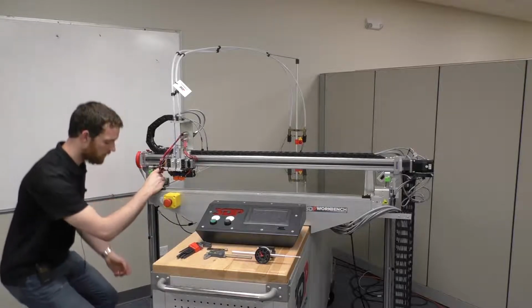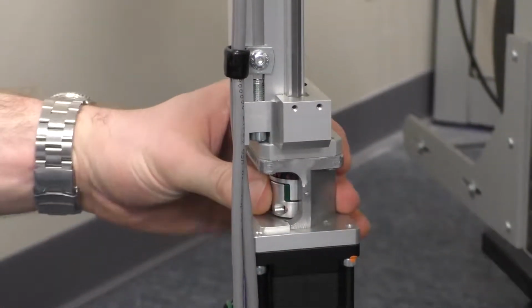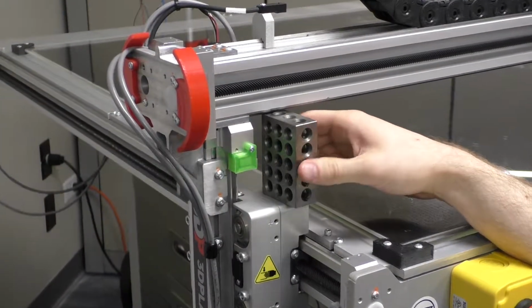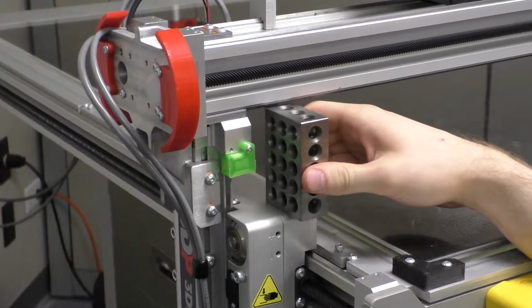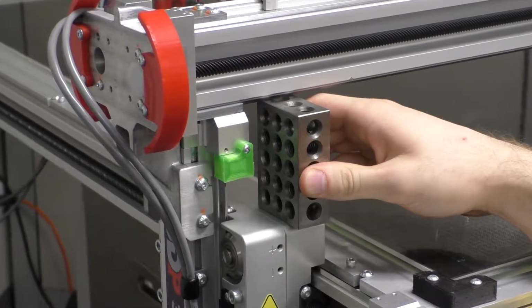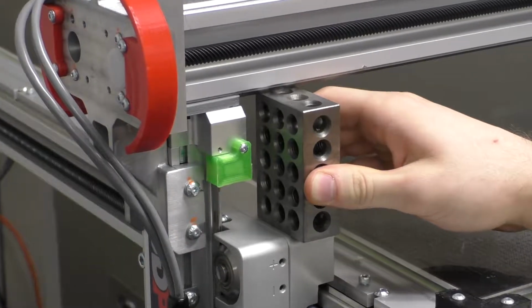And then we're going to go down to our motor coupling. We'll remove the black cover and turn the motor coupling by hand to move the axis up or down until it's just touching the top of the block. You should be able to slide the block in and out, but still feel some friction. We'll need to repeat this step for the other side.